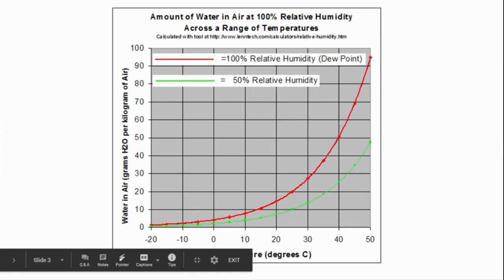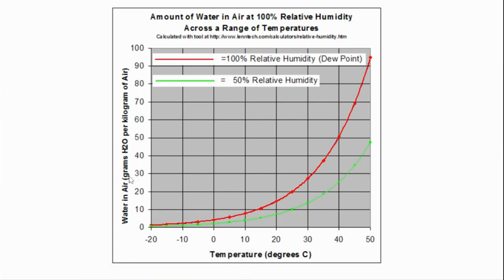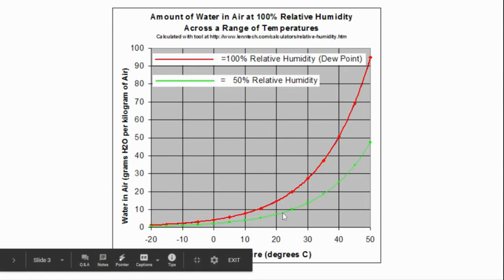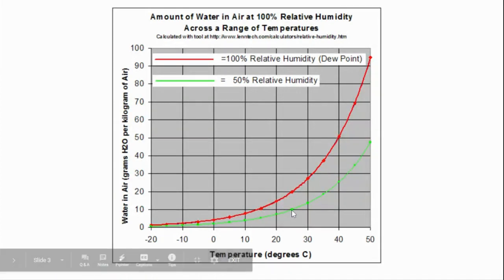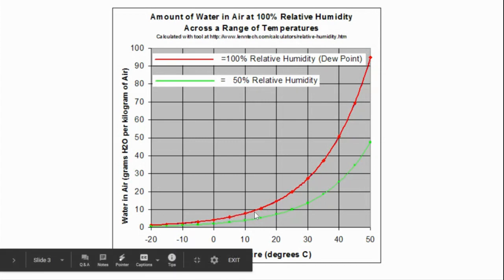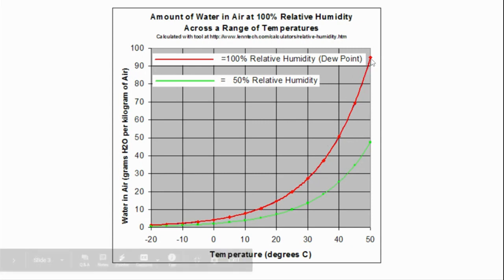Here's another way to look at this. We have a graph that shows the amount of actual water — the way we measure it is mass: grams per kilogram of air. So a big chunk of air and how many grams of water there is. Today it's about 20-25 degrees Celsius, so there could be 20 grams of water in the air, and there is 10 grams, which means it's 50% relative humidity. You can see what happens to the humidity — the ability to hold water — as the temperature goes up. 50 degrees Celsius is well above anything we could handle, but that's where it holds tons and tons — that becomes steam level where it holds a lot of moisture.